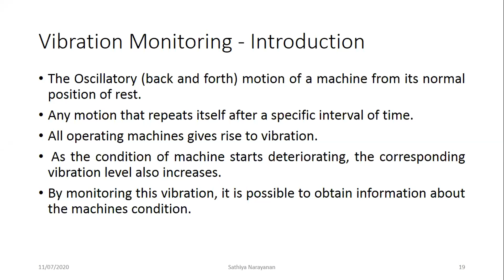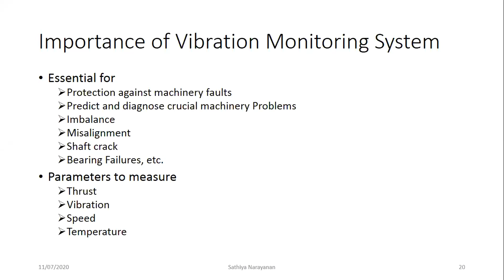So the importance of a vibration monitoring system is that each point is protection against a machinery fault. When there is a misalignment, or an imbalance, or a bearing failure, it is important to monitor the vibration. The other thing to keep in mind is the temperature of the particular pump, which shall be maintained within a particular range, because if it crosses, then it probably becomes a hazardous condition and we may have to trip the pump. And then the speed. In addition to the vibration, we also look at the speed. We always have an overspeed indication in all the turbines and all the motors, so that it does not cross a particular speed limit. If it crosses a particular speed limit, the machine may go out of control, and it may produce a hazard or even a blast in the worst case.